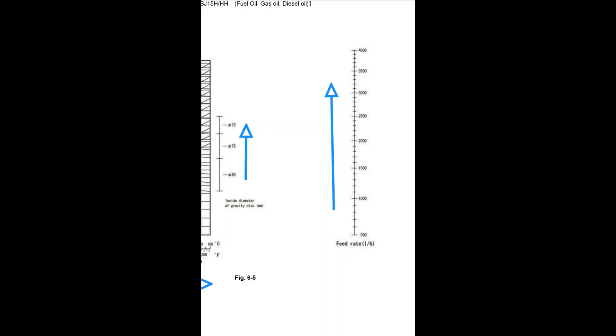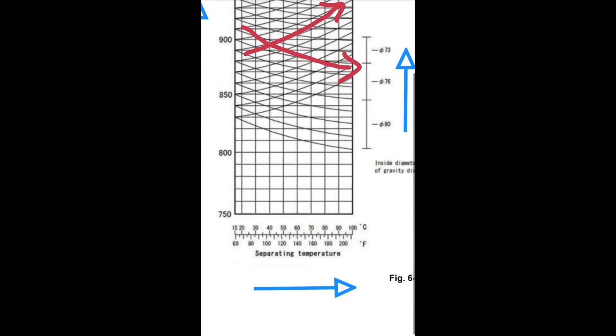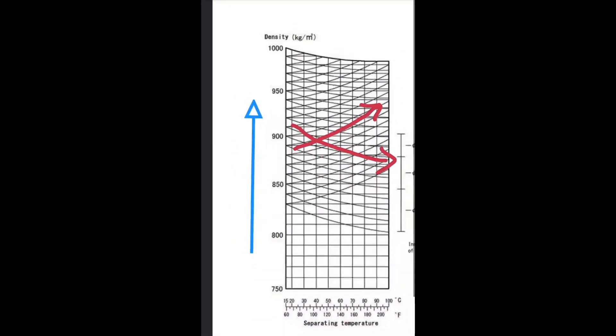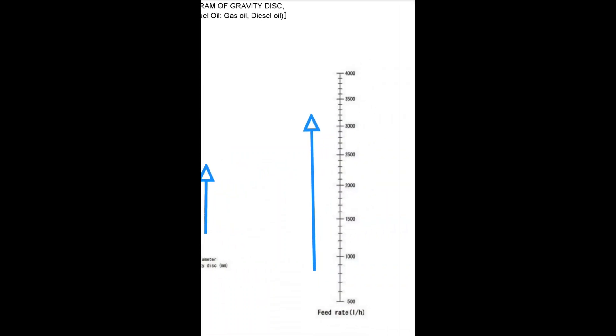On the extreme right, you can find the feed rate of the purifier in liters per hour. The feed rate is also known as the throughput of the purifier. For this model SJ15H, it is from 500 to 4000 liters per hour. You can also see that there are some rising curves as well as falling curves going from the density side to the right side. How these rising and falling curves play a role in deciding the gravity disk size, we are going to discuss that. So: bottommost is separating temperature, leftmost is density or specific gravity, there are rising and falling curves, inside diameter of the gravity disk in mm, and on the extreme right the feed rate in liters per hour.